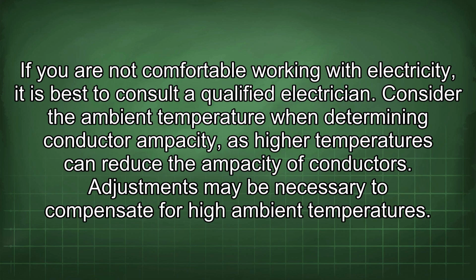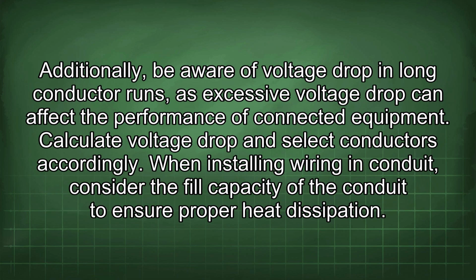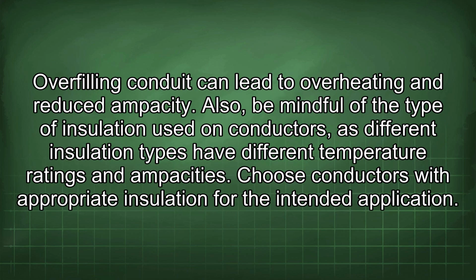Consider the ambient temperature when determining conductor ampacity, as high temperatures can reduce the ampacity of conductors. Adjustments may be necessary to compensate for high ambient temperatures. Additionally, be aware of voltage drop in long conductor runs, as excessive voltage drop can affect the performance of connected equipment. Calculate voltage drop and select conductors accordingly. When installing wiring in conduit, consider the fill capacity of the conduit to ensure proper heat dissipation. Overfilling conduit can lead to overheating and reduced ampacity. Also, be mindful of the type of insulation used on conductors, as different insulation types have different temperature ratings and ampacities. Choose conductors with appropriate insulation for the intended application.